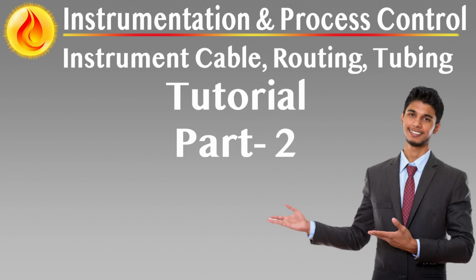Earthing of intrinsically safe circuits. Safety barriers and galvanic isolators used in intrinsically safe loops must be connected to the safety earth unless a manufacturer-approved dedicated earth is specified. Earthing must be secure, direct, and capable of handling potential fault currents without exceeding resistance thresholds that could compromise intrinsic safety compliance.